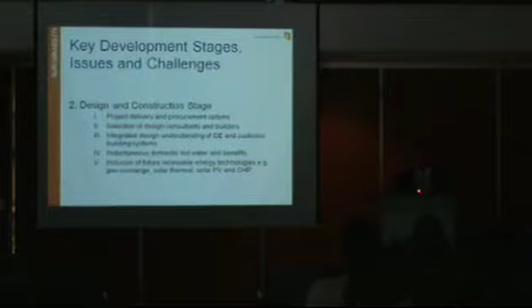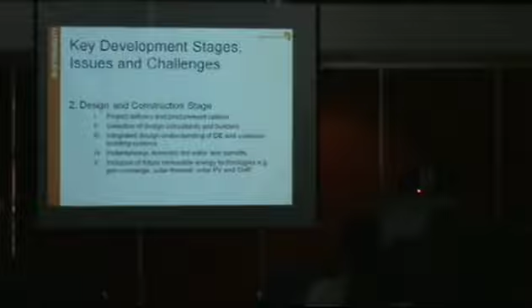They may not be fully conversant with how to do the interface. So if they are using a constant flow design, whereas the central system's efficiency depends on variable speed design, then you have to sit down and openly discuss how the secondary or building system design is compatible with the central plant design. That's what integrated design, point number 3, is all about.